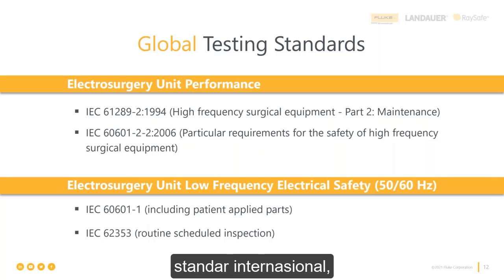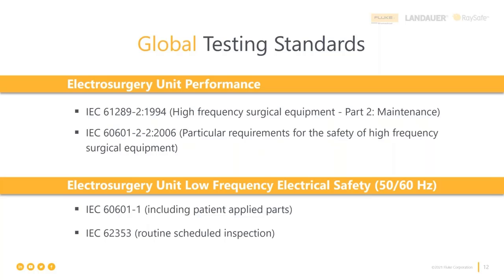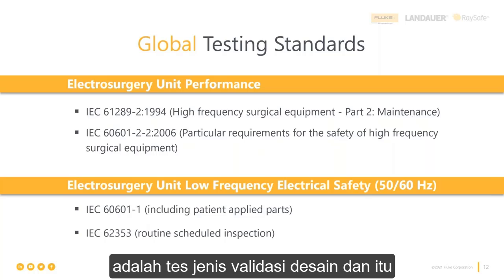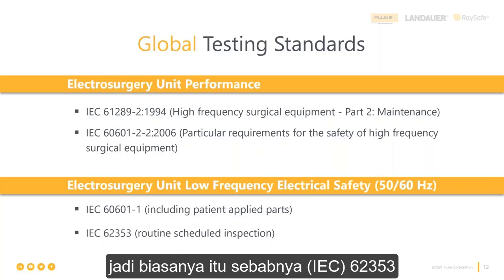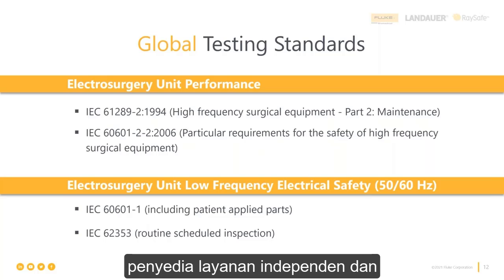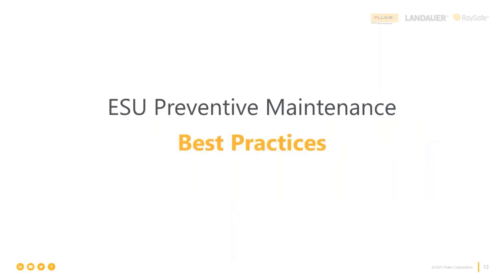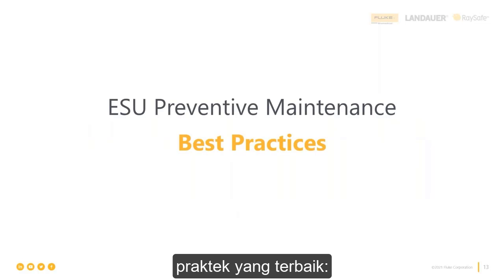You'll never be wrong if you're using and testing to the international standards. Just remember that the IEC 60601-1 is a design validation type test, and it includes tests that could shorten the useful life of the medical device. So typically that's why 62353 would be the more applicable to those of us that are in hospitals or are third-party service providers, independent service providers, testing ESUs across a variety of different clinical facilities. All right, so here are some best practices.